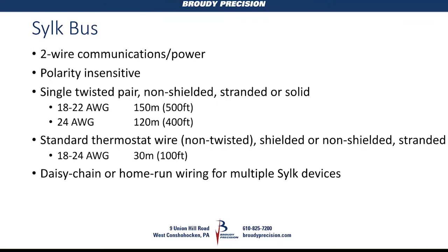Your best and longest run uses a non-shielded twisted pair, 18 to 22 gauge. You can daisy chain or home run your wiring back to the controller, so you can have multiple Sylk devices.